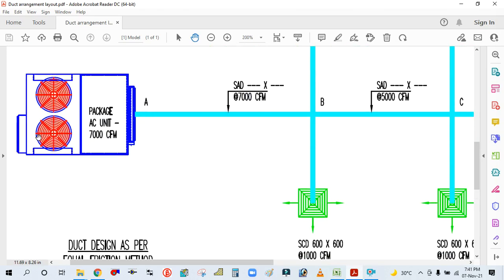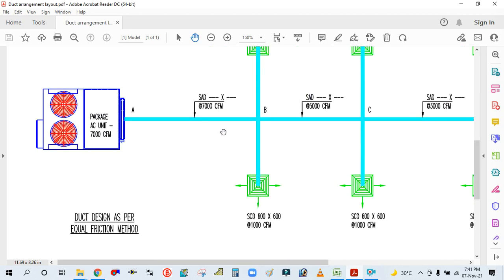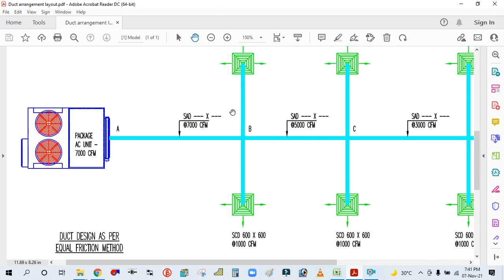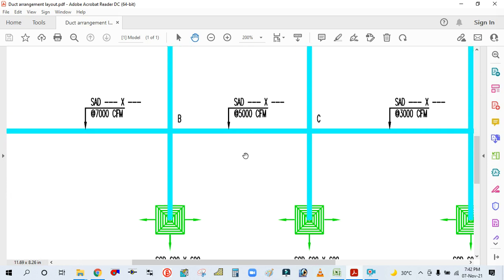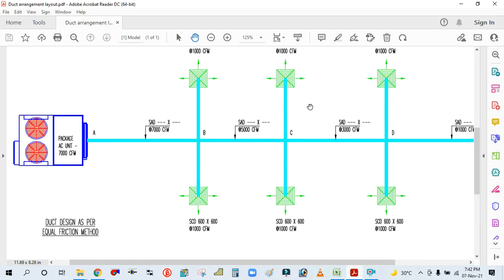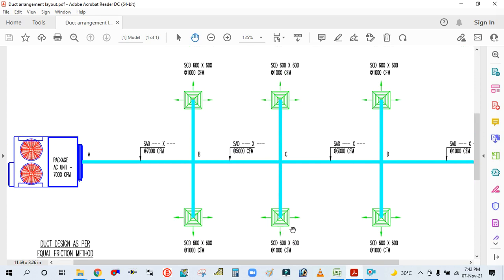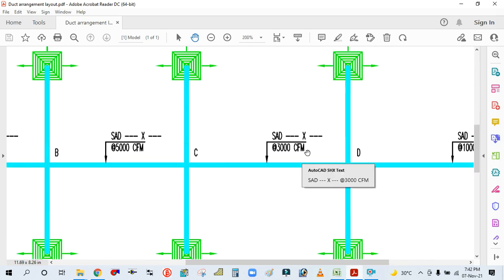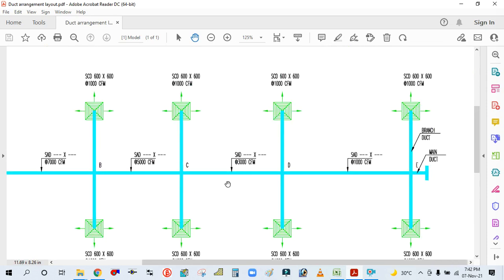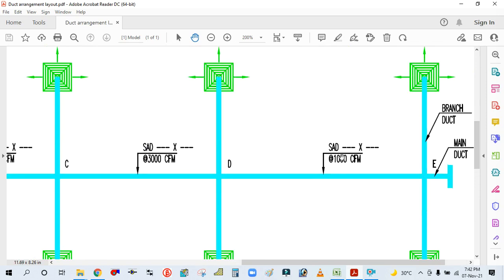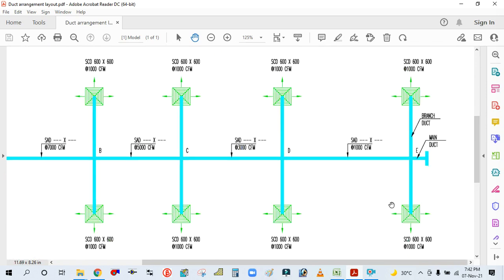The total CFM for this package air conditioning unit is 7000 CFM delivered. It will supply 1000 CFM to each diffuser here, and then 5000 CFM passes through this section supplying 1000 CFM to these two diffusers. The remaining 3000 CFM passes through this duct supplying 1000 CFM to these two diffusers.